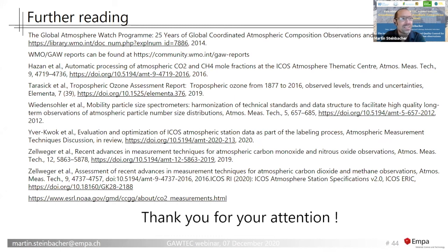We rather suggest to track the sensitivity, and the sensitivity changes with time, and then you can fit some low pass filter, let's say, through the background signal of the instrument, or when you apply a specific concentration, because often it goes a little bit up, then it goes a little bit down. And you can easily correct for that afterwards with some suitable tools.